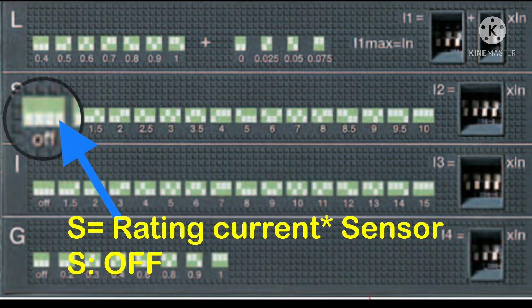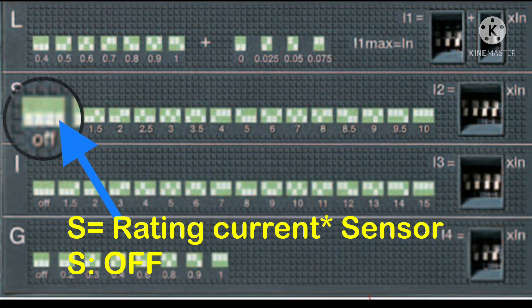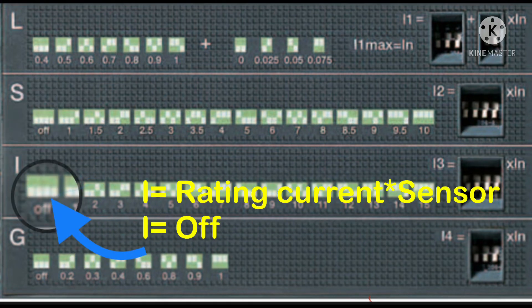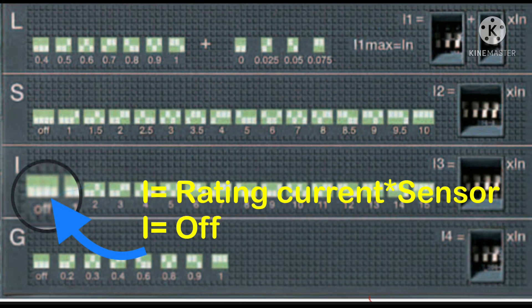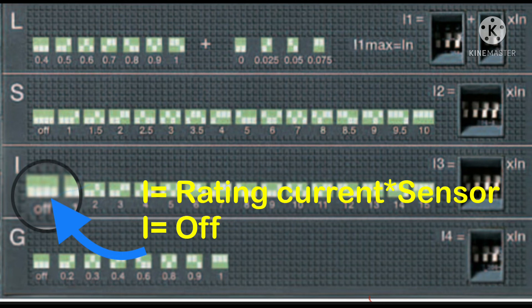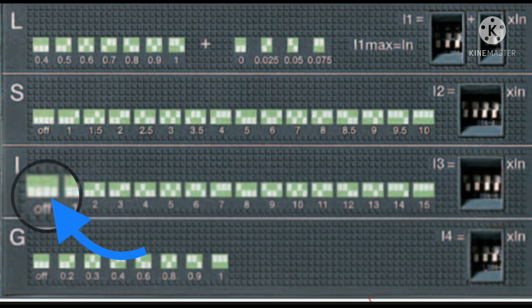to 10, we would multiply the rating by 10. That means multiplying 1000 by 10, our short time current setting would be 10,000 amperes.